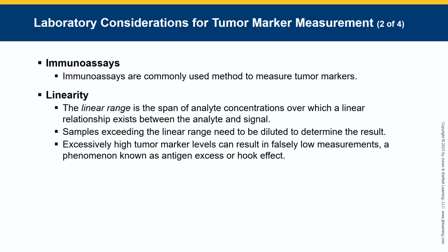Immunoassays are commonly used method to measure tumor markers. Linearity, the linear range is the span of the analyte concentrations over which a linear relationship exists between the analyte and signal. Samples exceeding the linear range need to be diluted to determine the result.